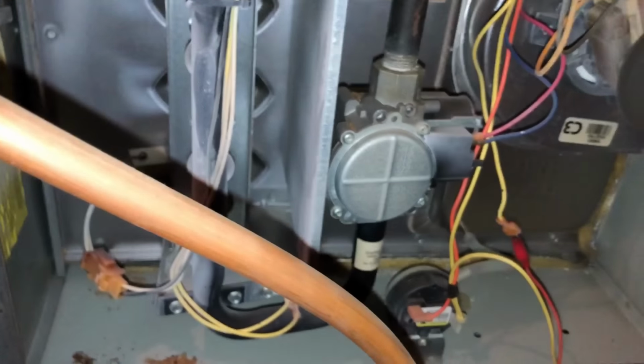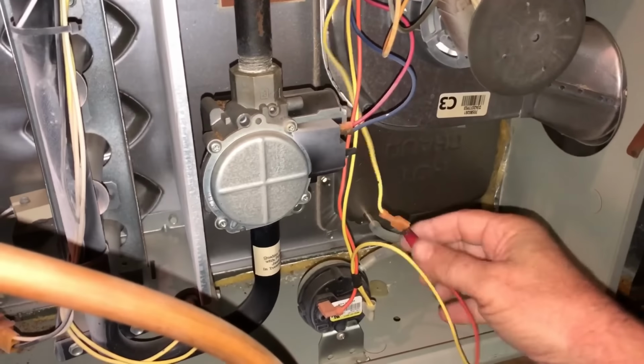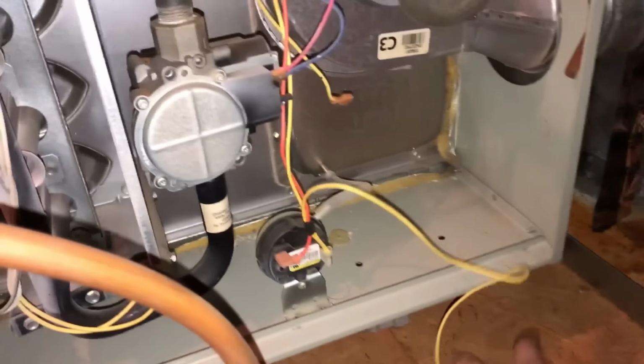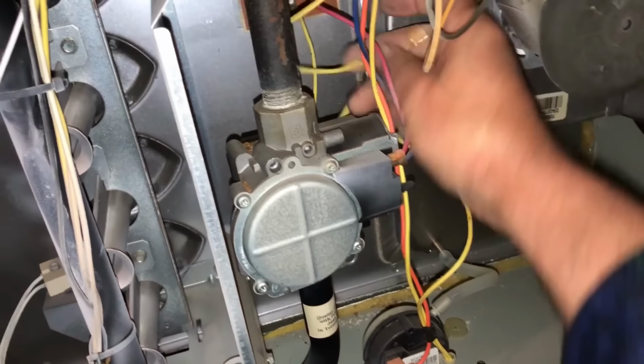Okay. And we started out with no error code, and the induced draft started. I guess it's possible this one is bad. So in order to determine if it's the board or one of these little devices, just gonna go through here one at a time, taking them out of the mix.